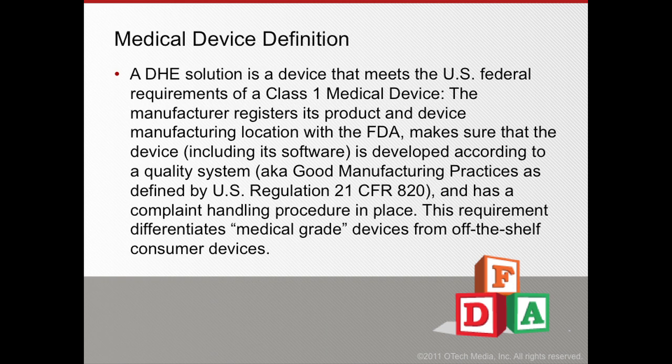That means that the manufacturer registers its device and the product within the FDA. So if anybody that uses the same device has a major problem — for example, the images do not appear anymore, or they appear inverted, upside down, or left-right inverted — the user could call the FDA and say, 'I have this product, this medical device from this vendor, and I want to report it so you, Mr. FDA, please notify the manufacturer and all the users of this product so that they are aware of this problem, so we don't have any potential patient care impact.' So that's the importance of the registration of the medical device with the FDA.